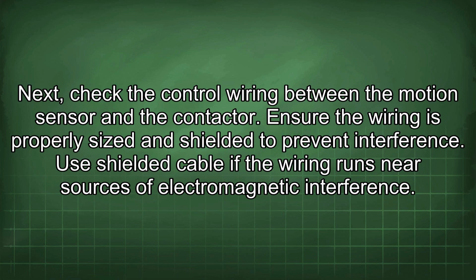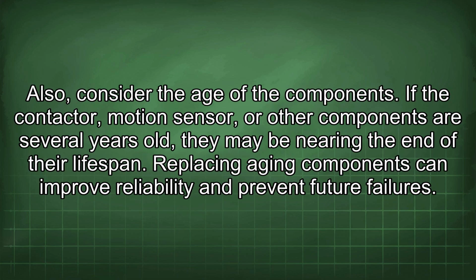Next, check the control wiring between the motion sensor and the contactor. Ensure the wiring is properly sized and shielded to prevent interference. Use shielded cable if the wiring runs near sources of electromagnetic interference. Also, consider the age of the components. If the contactor, motion sensor, or other components are several years old, they may be nearing the end of their lifespan. Replacing aging components can improve reliability and prevent future failures.